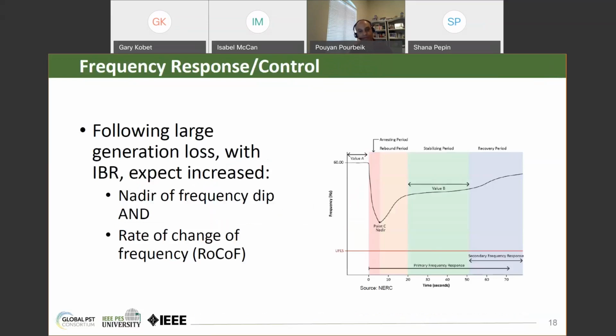in terms of frequency response, on the right-hand side you see what you would expect in a typical scenario on a grid when you have, say, loss of the largest generator. Your frequency being, at least in North America, at 60 hertz, you lose some generation. Initially, you have that darker red or pink area where you have a decline in frequency driven by the inertia of the system, so the rate at which frequency drops. Then you get to that nadir point C, and at that point your conventional turbine governors start to kick in and provide primary frequency response, so the curve turns around, frequency starts to pick up, and then finally settles down and stabilizes in that green area, the region of new equilibrium. And then finally, in that purple area at the end, things like AGC, secondary control, come in and bring the frequency back up to 60 hertz.